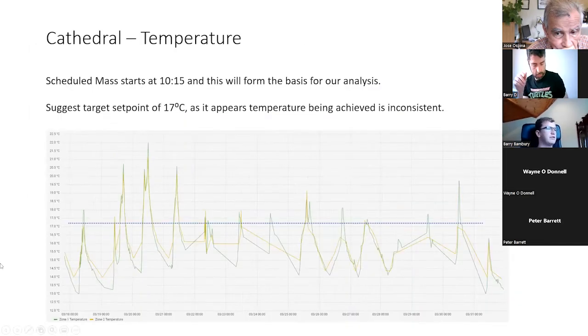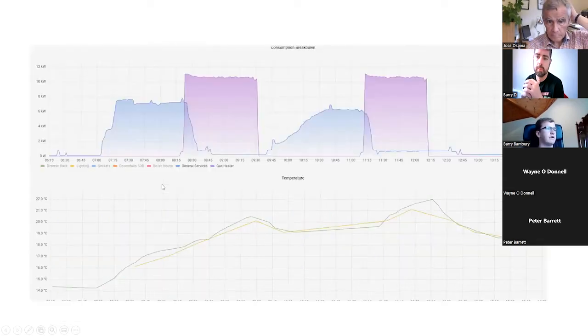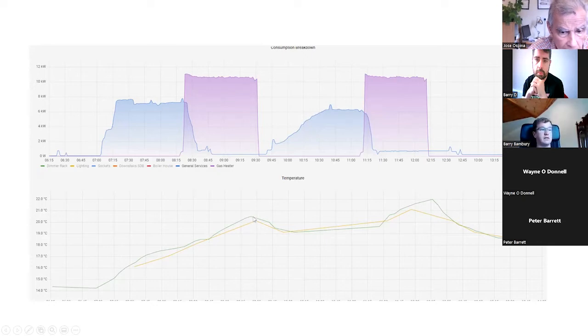So what I've done here is I've just zoomed in on one of the days that it overheated, just to give you an idea. Usual story: the air source heat pump comes on in the morning, supplemented by the gas heater. The gas heater runs, the air source heat pump turns off. At this stage, we're up to 20 degrees Celsius at both our temperature probes, so we'd be very confident that what we're recording is right. This turns off, you have a small drop, and then it settles around here. But the air source heat pump comes back on. So we're at 19 degrees Celsius, and the air source heat pump comes back on and tries to raise the temperature within the space.